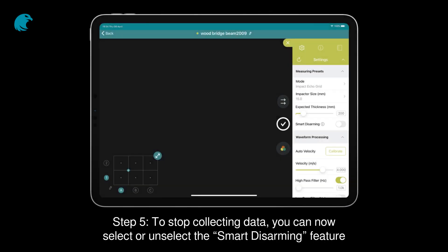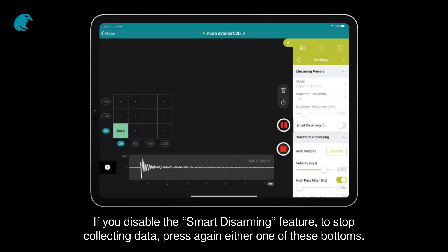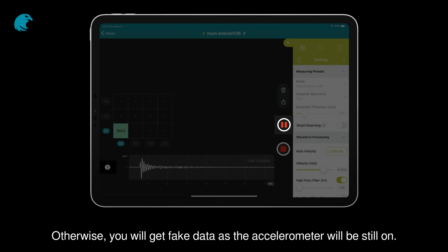Step 5. To stop collecting data, you can select or unselect the smart disarming feature. If you disable the smart disarming feature to stop collecting data, press again either one of these buttons. Important: do not separate the device from the wall before disarming it. Otherwise, you will get fake data as the accelerometer will still be on.